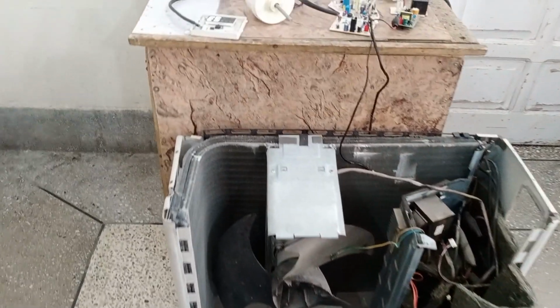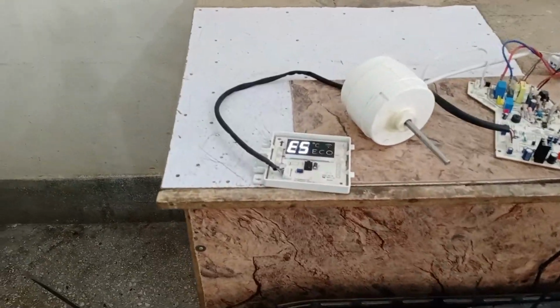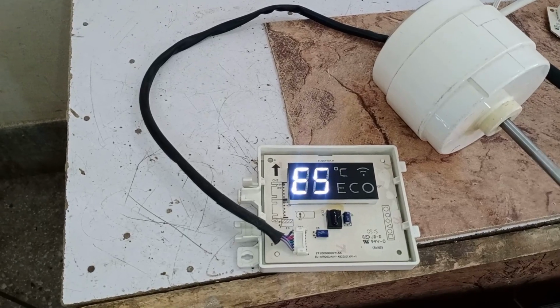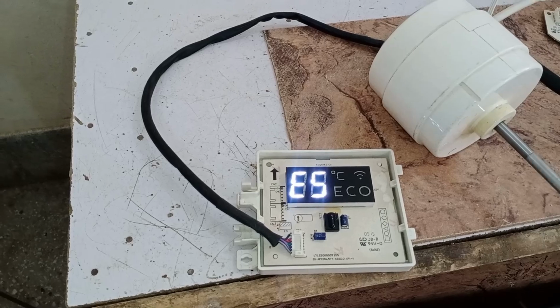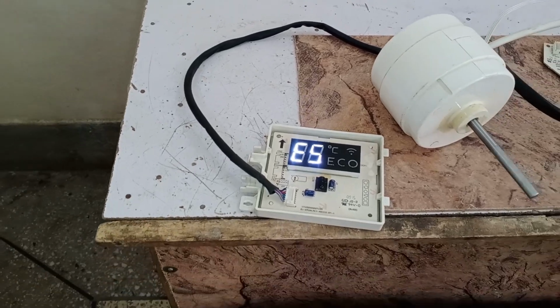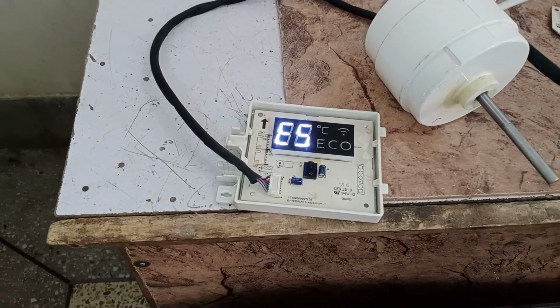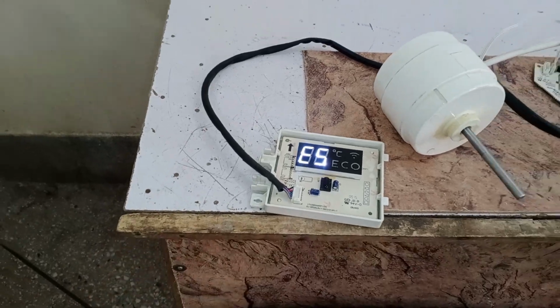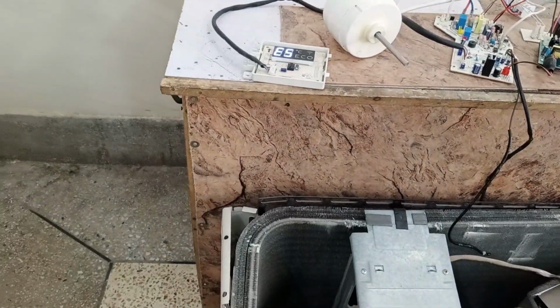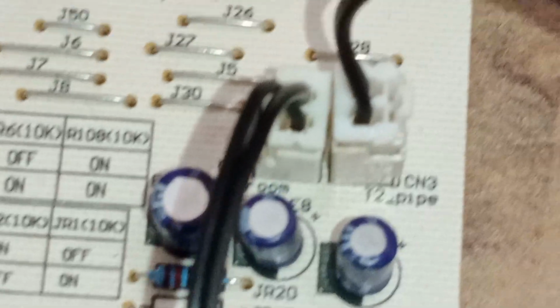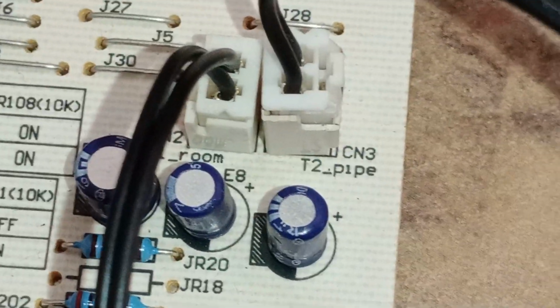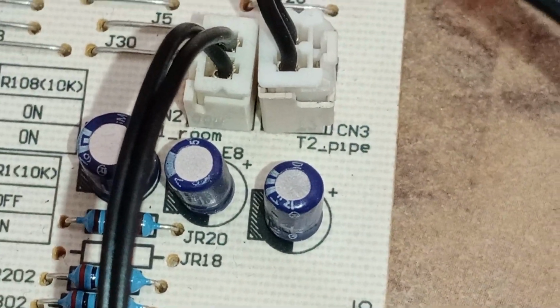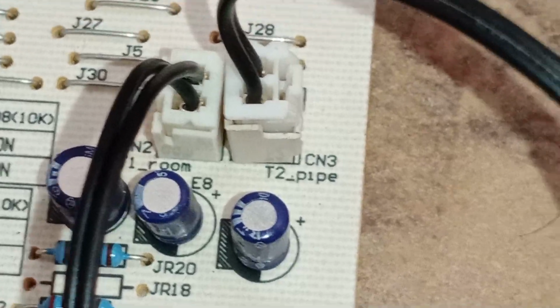Now let's look at the next error code, which is E5. For a standard 1.5 ton unit, the E5 error represents something different. However, when it comes to a 2-ton unit, apart from the room temperature sensor, there is another sensor installed, which is the pipe coil sensor. Let me show you its position. Now you can see the second sensor installed here, which is the pipe coil sensor, labeled as CN3T2 pipe. This is the pipe coil sensor.